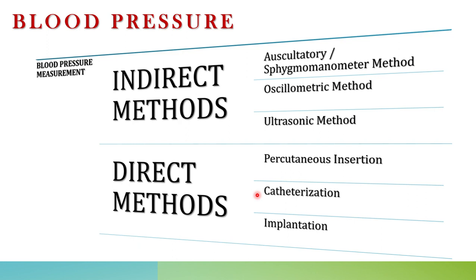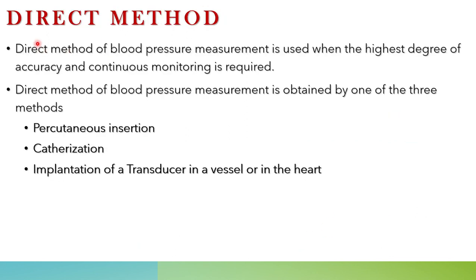In this class we are going to discuss the direct methods: percutaneous insertion, catheterization, and the implantation of a transducer in the blood vessel. The direct method of blood pressure measurement is used when a higher degree of accuracy and continuous monitoring is required. In indirect methods, accuracy is less and there is a chance of errors, and continuous monitoring is not suitable.